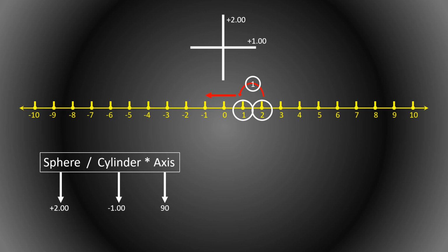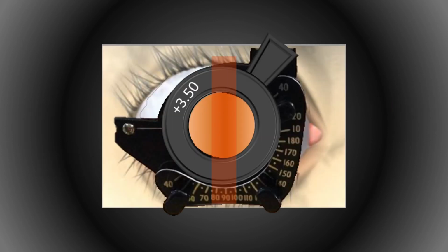And the other method to solve a power cross I mentioned in the lensometer part 1 video. The link for that I am providing in the description below. And this was the method of neutralization with two spheres. Now we'll see the spherocylinder method. For the spherocylinder method, I start when we have one meridian already neutralized with plus 3.5 diopter. Now rotate the streak 90 degrees away from this meridian.